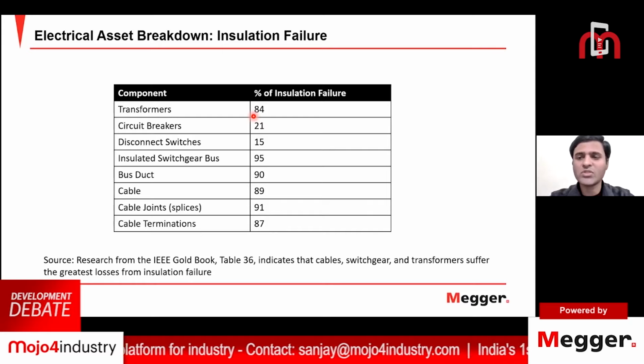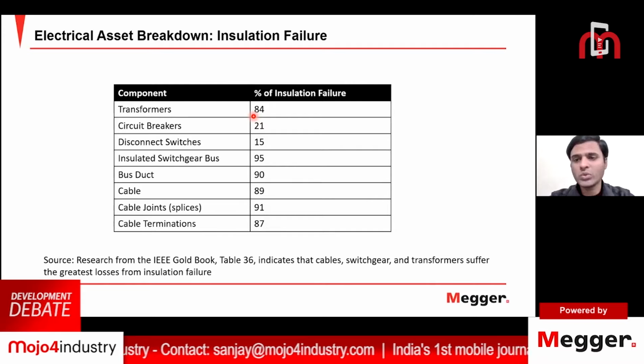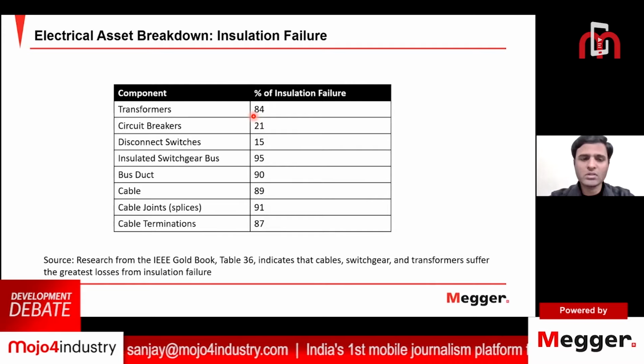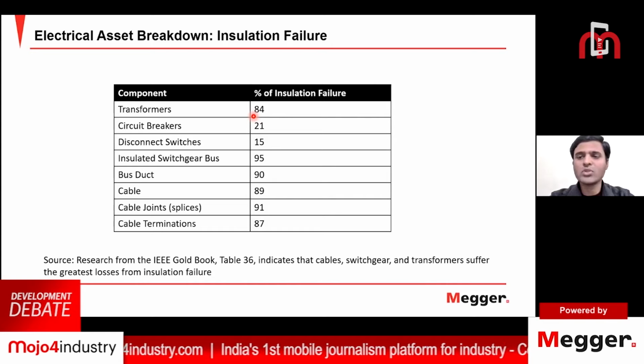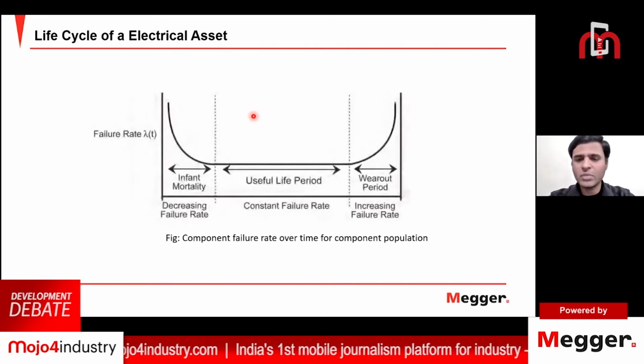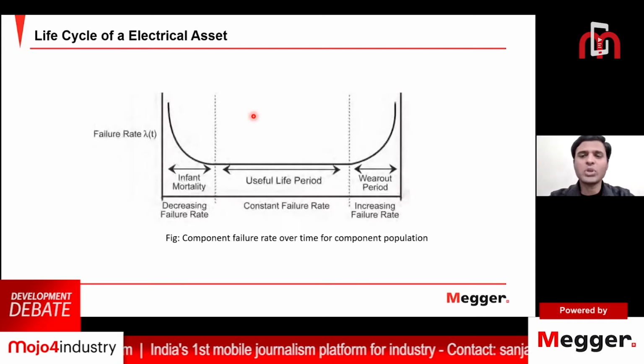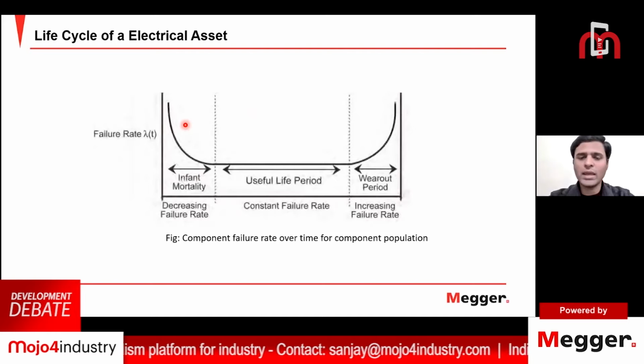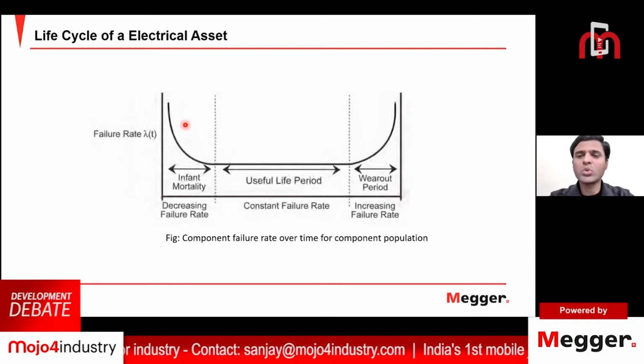Circuit breakers also face failures, and 21% of failures are due to the insulation failures in the circuit breakers. Cables, which are a major part of electrical assets because they are responsible for the transmission of electricity from one place to another place, 90% of the cable failures are due to the insulation failures in their components. And so it's very important that we do periodic monitoring of the insulation. So the failure rate graph is like a bathtub curve. That means whenever an electrical asset is put into service the first time, there can be a large failure rate. It may be due to a human error, or it may be due to a low quality material used in the manufacturing of that particular electrical asset.